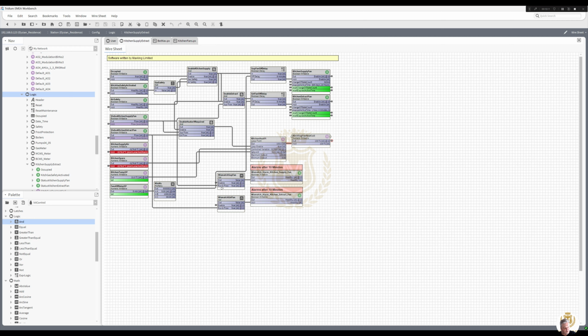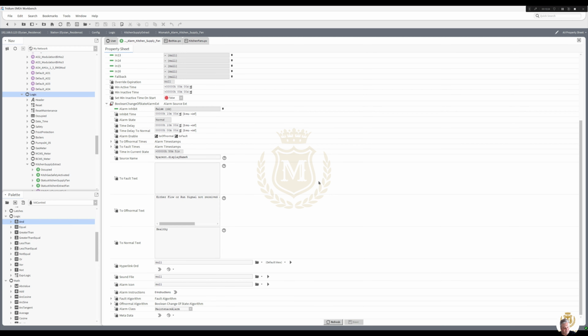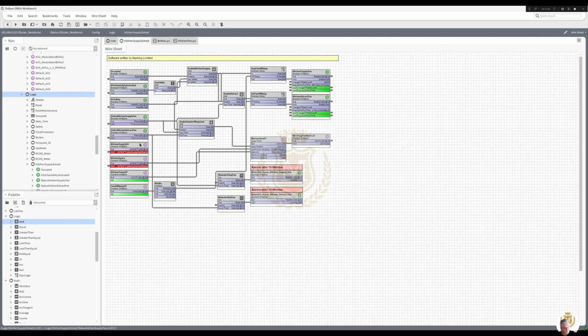We've got a mismatch alarm. So we use an XOR gate and we monitor the flow and we monitor the enable, and as long as they're both true, we're okay, or they're both false, we're okay. But if either one of them is true, then we put the alarm on, and inside here I've basically set it for 10 minutes. Inhibit time 10 minutes. So it won't come on for 10 minutes. I just didn't bother putting a timer, I just put an inhibit time.